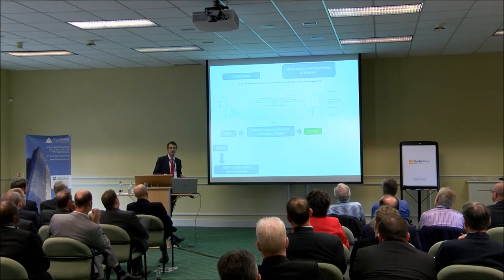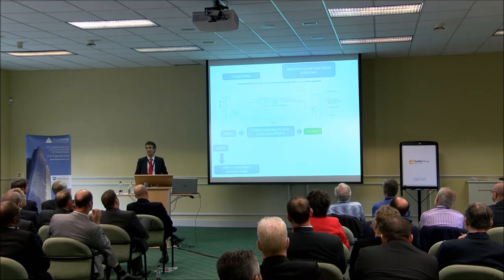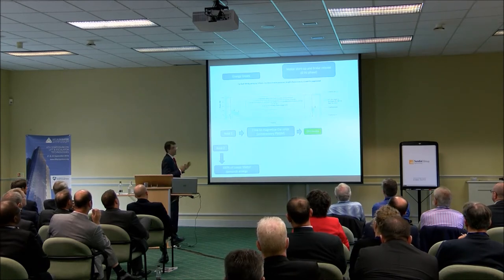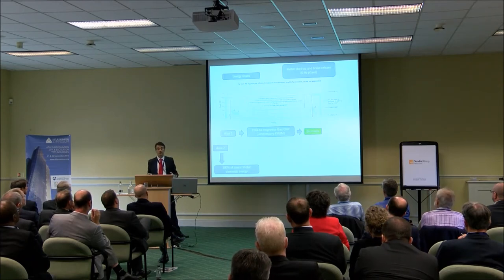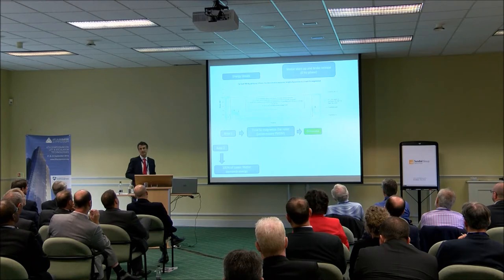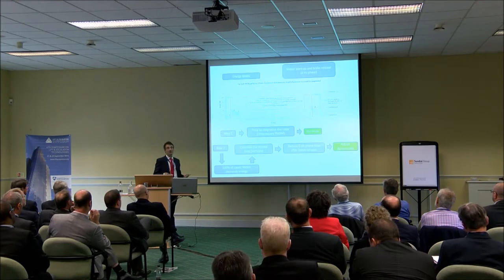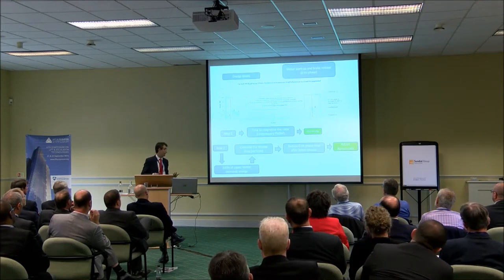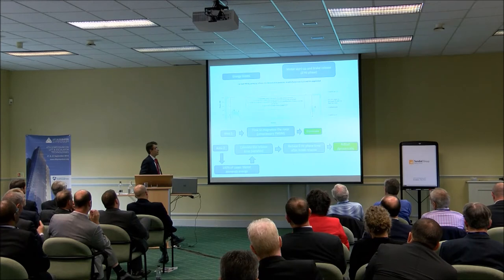If we look at area number two, this is the area after the brake release command is given. The area below the blue line represents the energy. Area number two in all cases generates energy demand in the lift. What we suggest here is to adjust it dynamically — we would like to calculate the release time and try to reduce this phase time as much as possible.